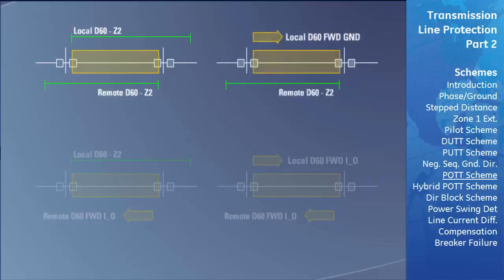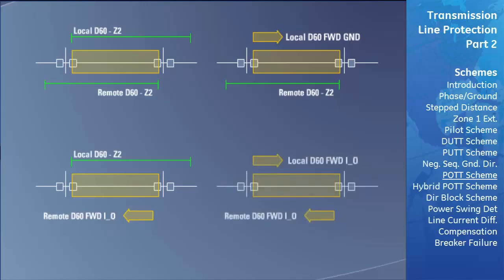In diagram 1, if Zone 2 of both relays identifies a fault, it is a clear indication the fault is on the transmission line and both relays trip. In diagram 2, the remote Zone 2 indicates the fault is to the left of the remote relay, and the forward flow of ground current seen by the local relay indicates it is to the right—therefore on the transmission line, and both relays trip. In diagram 3, forward flowing ground current at the remote relay and Zone 2 pickup at the local relay confirms the fault is on the line and both breakers trip. In diagram 4, ground current flowing into the transmission line as detected by both relays confirms the line is faulted and both breakers trip.